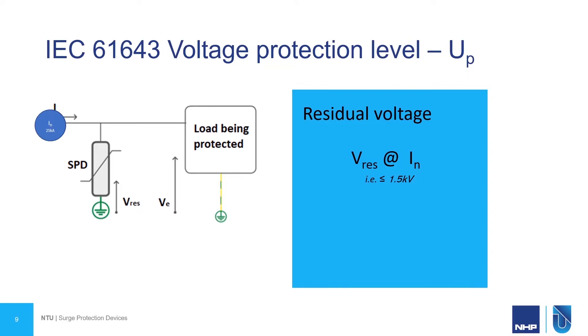UP is the voltage protection level. This essentially is the residual voltage that is left over an SPD when it's tested at its nominal current rating. So in our example, the SPD had an IN nominal current rating of 25 kA and a voltage protection level UP of less than or equal to 1.5 kV. So when the SPD sees a surge of 25 kA, you know that the residual voltage is going to be less than or equal to 1.5 kV. Essentially, this is the most important factor when looking at protecting our loads.